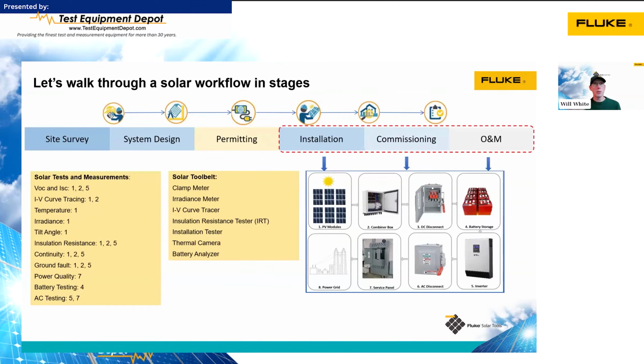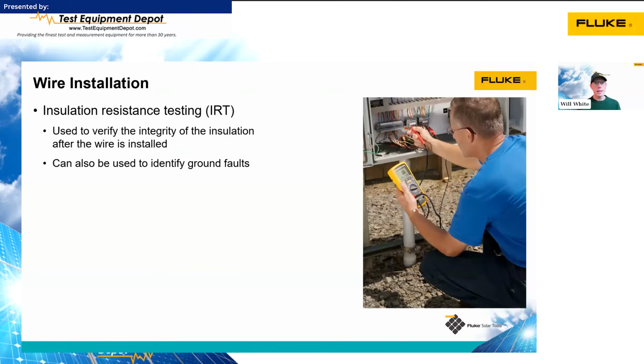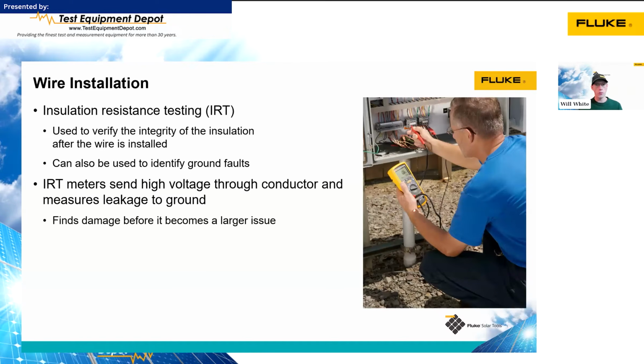Now, in this presentation, we're going to look at the installation, commissioning, and operations and maintenance sections of the system life cycle, because that's where the testing is done. And as a test equipment manufacturer, that's what we're mostly concerned with. So during installation, there's a couple tests that we're going to do. The main one is insulation resistance testing. This is going to be used to make sure that the insulation hasn't been compromised during installation. We're also going to use it to identify locations of ground faults.